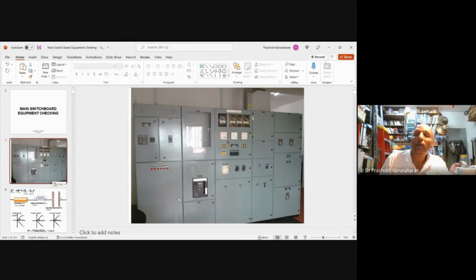So why do you have so many things here? In most MSB, you just have indicator bulbs, fuses, and the selector switch - that's the standard. In this school, they have the old type with 3 overcurrent and 1 earth fault, a new type with OC and earth fault, and a super new type with OC and earth fault together. But most technicians don't like this one - if OC and earth fault are together, when it trips, both go at once. At least with separate ones, if one is spoiled, the other can still protect the building a bit. That's why most people don't like the combined type.